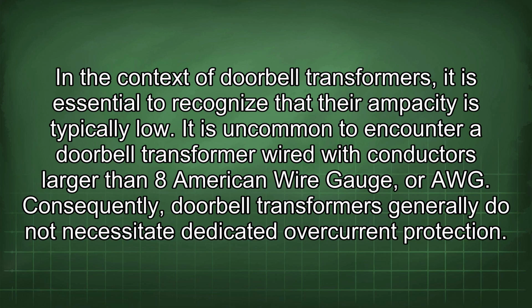In the context of doorbell transformers, it is essential to recognize that their ampacity is typically low. It is uncommon to encounter a doorbell transformer wired with conductors larger than 8 American Wire Gauge, or AWG. Consequently, doorbell transformers generally do not necessitate dedicated overcurrent protection.